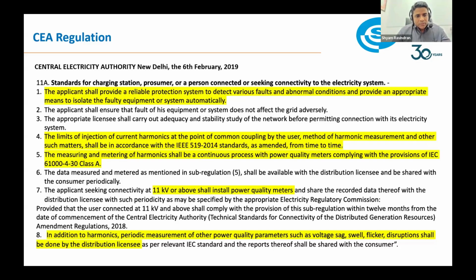Point number 5 talks about the measuring and the metering of harmonics, which shall be a continuous process with power quality meters complying to IEC 61000-4-30. It shall be a continuous process and the equipment shall have the necessary standards backing it up. Why the standards? I will share in the next slides why this Class A is mentioned and what is the significance of it. Yeah. Then comes point number 4.